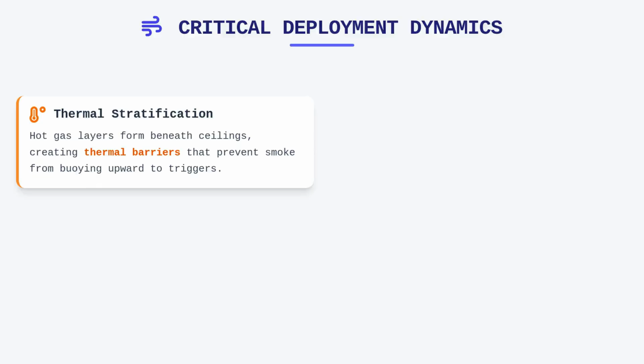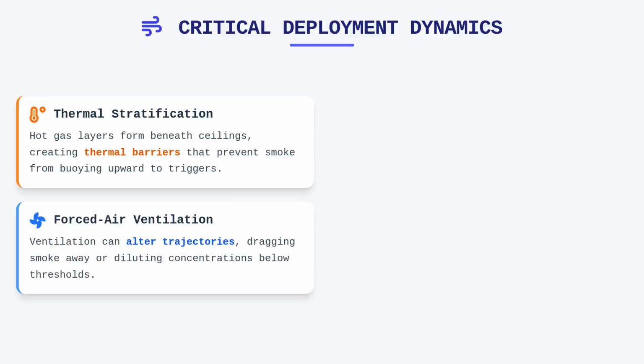Successful deployment is rarely just about the device hardware. It is about accounting for the fluid dynamics of the building itself. Smoke behavior is heavily influenced by thermal stratification, where a layer of hot gas forms beneath the ceiling, creating a thermal barrier that may prevent smoke from buoying upward to trigger detectors. Furthermore, the presence of forced air ventilation systems can significantly alter smoke plume trajectories, dragging smoke away from detectors or diluting its concentration below threshold levels.